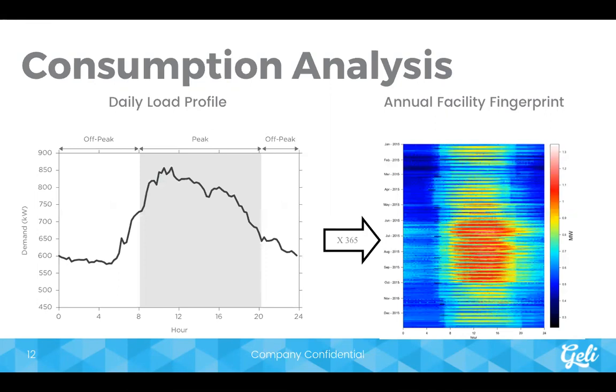On this day we grabbed, I think it was a March day, the peak load is about 850 kilowatts. So it's not the max peak I talked about, over a megawatt, but it's pretty high. If you take this daily load profile and stack 365 of them on top of one another, you get the image on the right.